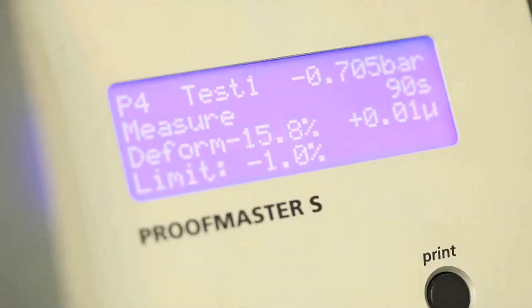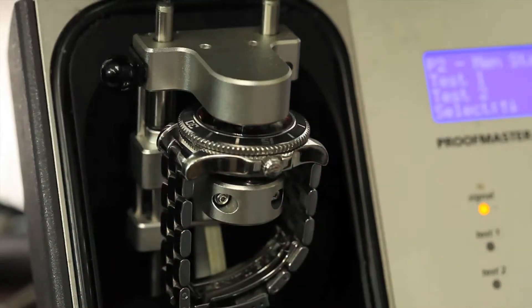Upon closing the chamber, which locks automatically, the device generates a moderate pressure within that's calibrated to the tolerance of the item inside it. Since the machine is able to test plastic, ceramic, and steel watches, our watchmakers set the parameters of each test individually.